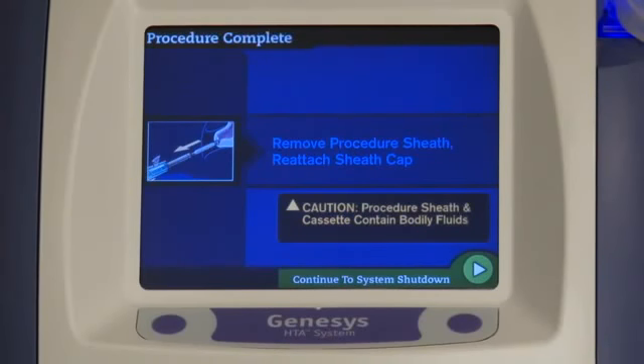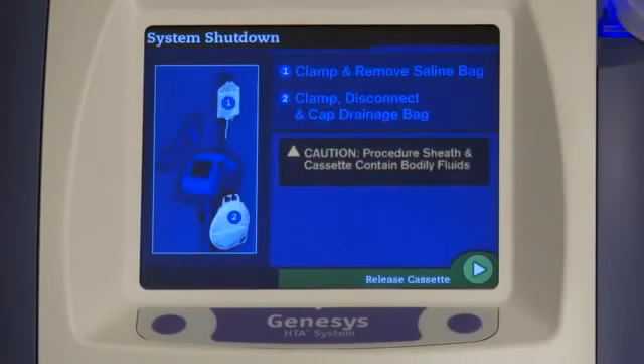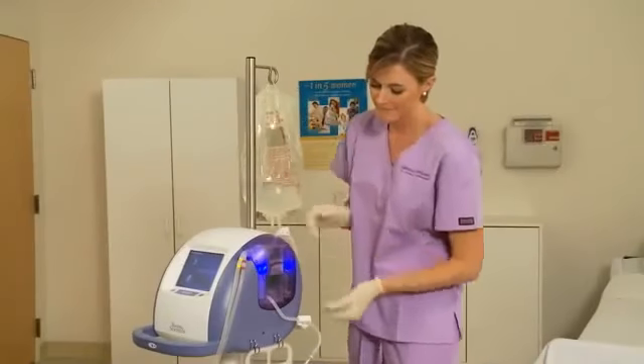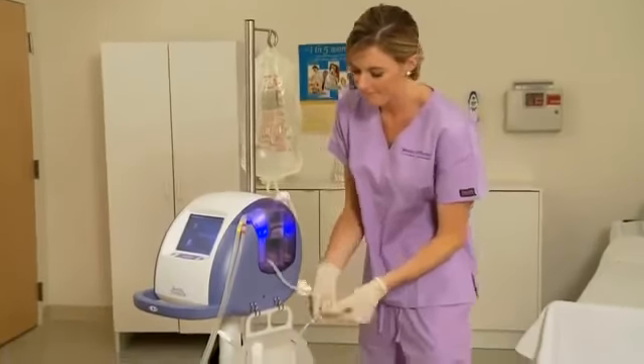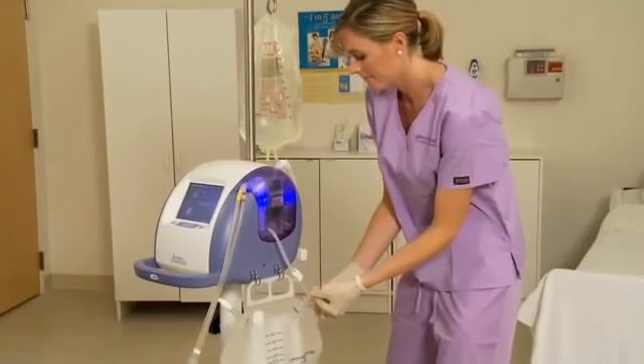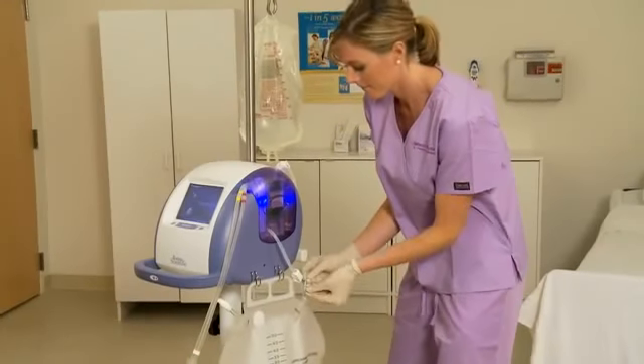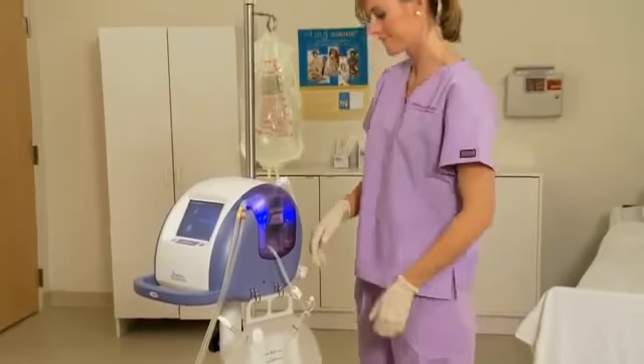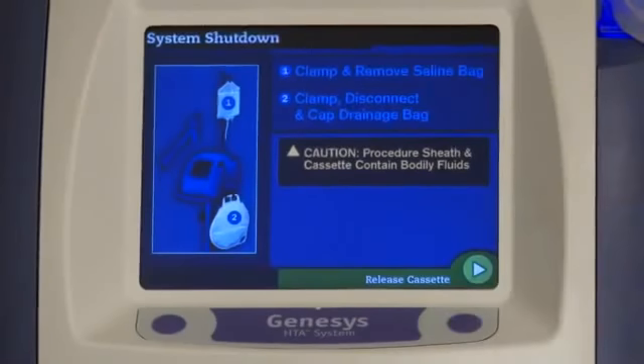You will be prompted to remove the procedure sheath from the cervical canal and reattach the sheath cap. Press the right console button to continue with system shutdown. Next, the system will instruct you to clamp the saline bag. Then clamp, disconnect, and cap the drainage bag. To release the cassette, press the right console button. System shutdown is now complete.